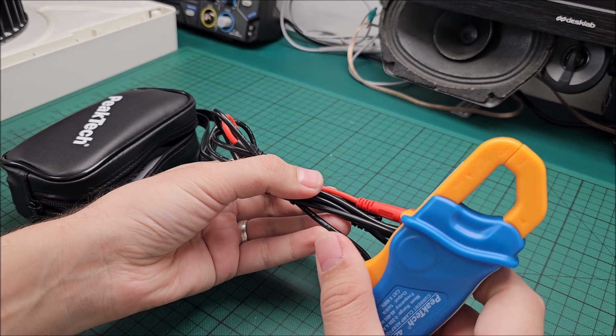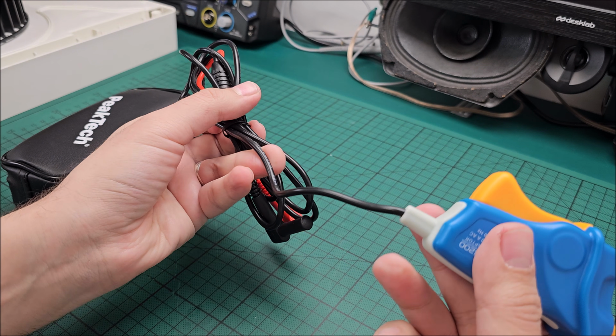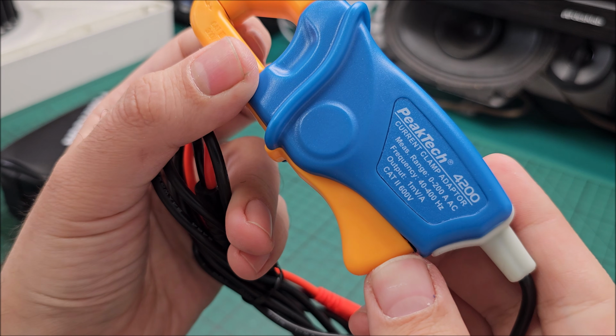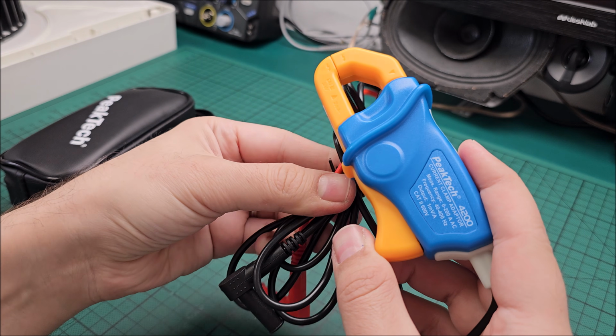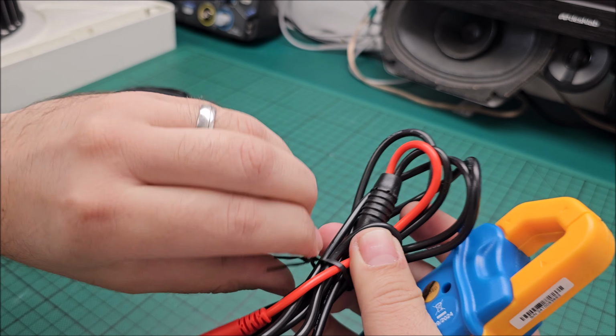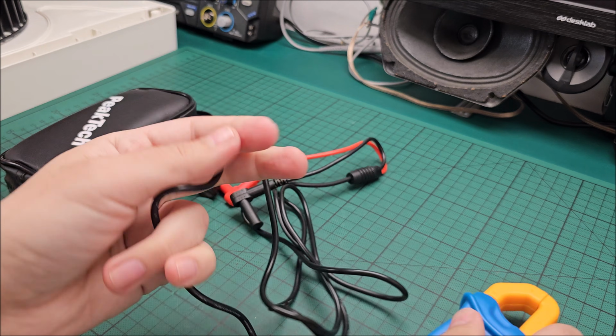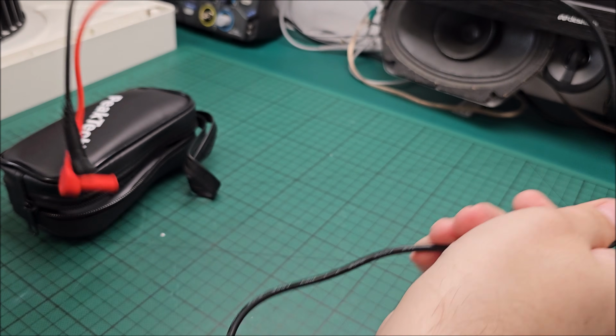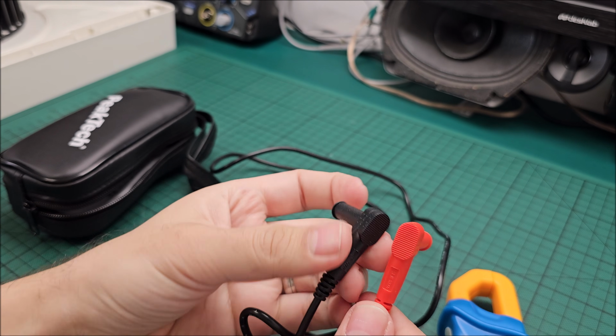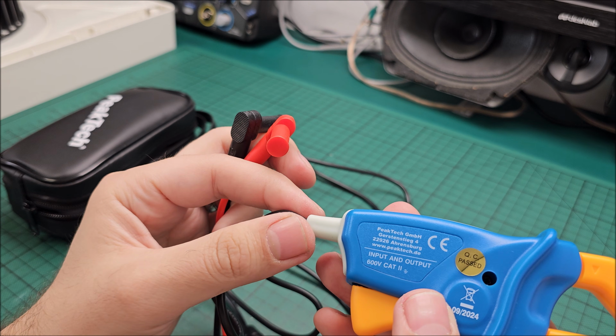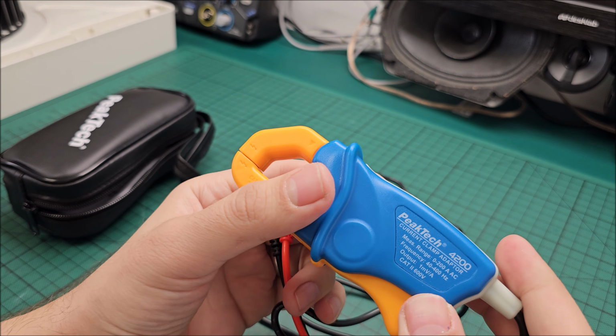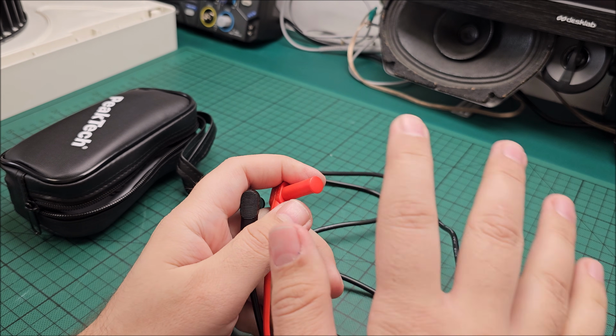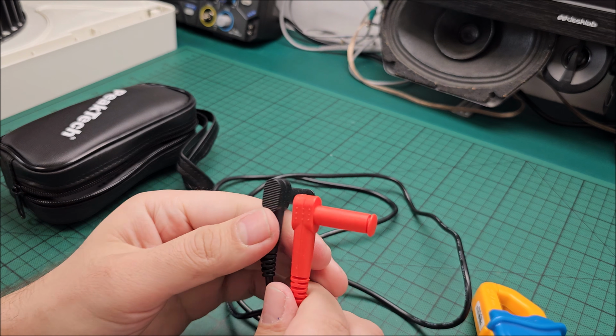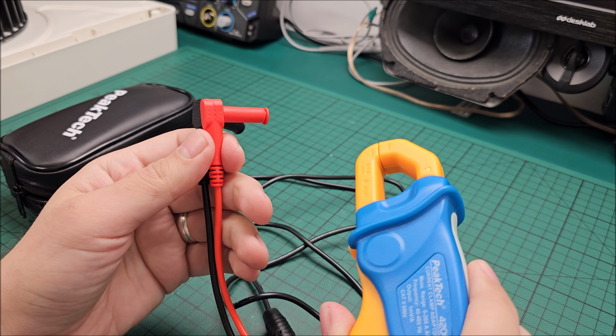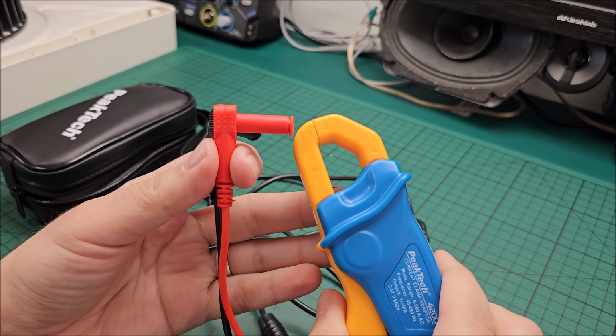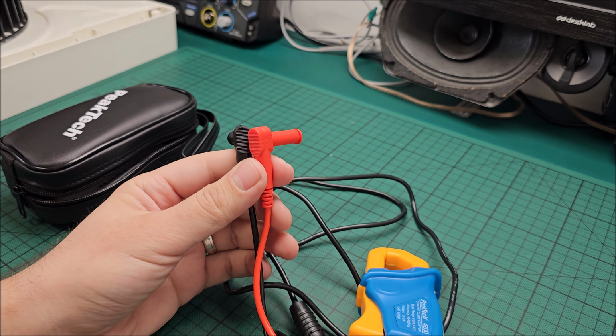So what I'm seeing now, okay, so it's one wire coming out of the probe itself, and then it splits into 2 wires, so it can connect to your standard multimeter. What's important is that the multimeter actually has a millivolt AC reading, because otherwise you would just have a bit of a not so precise measurement. You can still get a guess of what's going on, but the more precise your reading is on the multimeter, the better you will understand the situation.